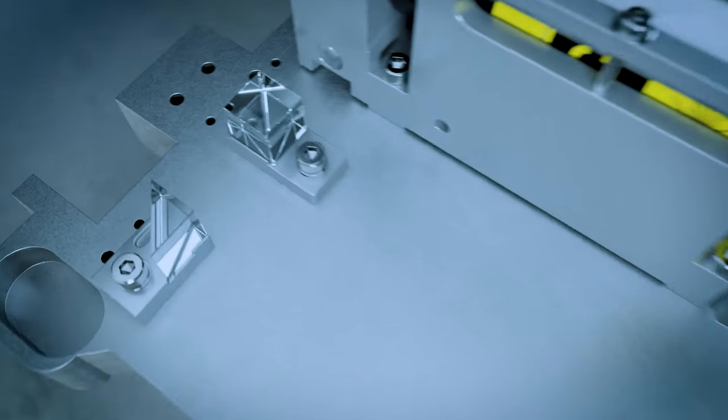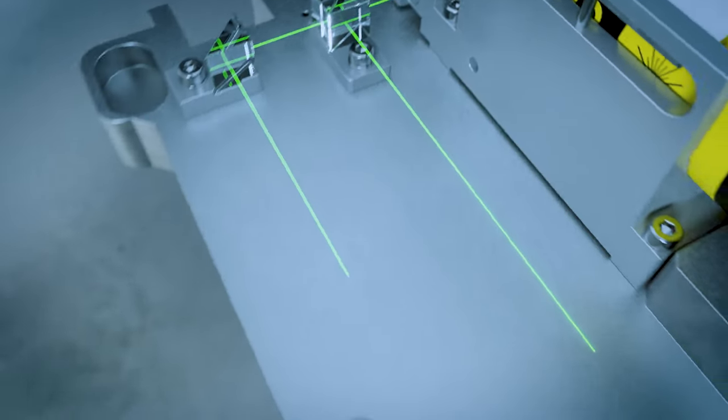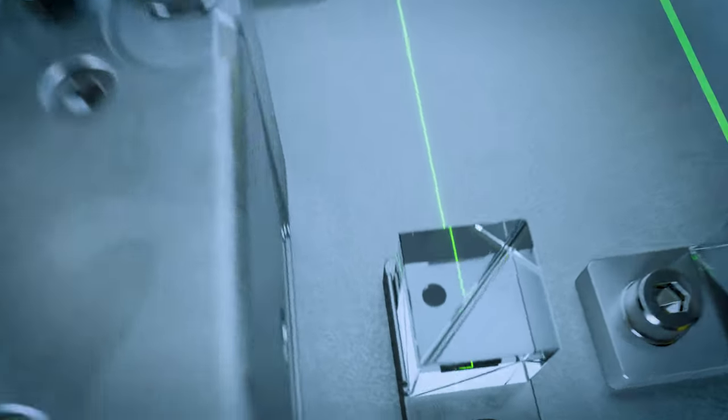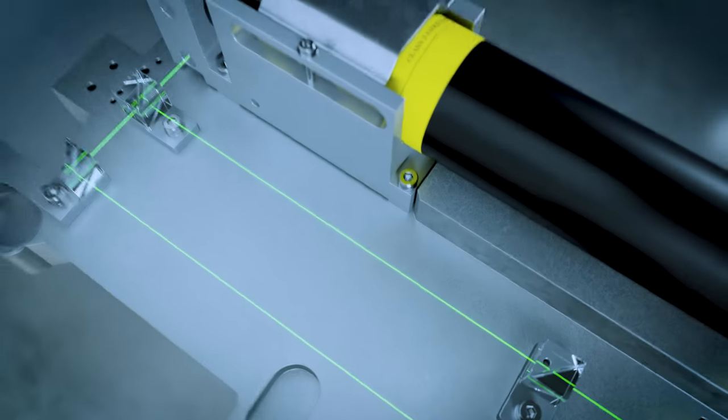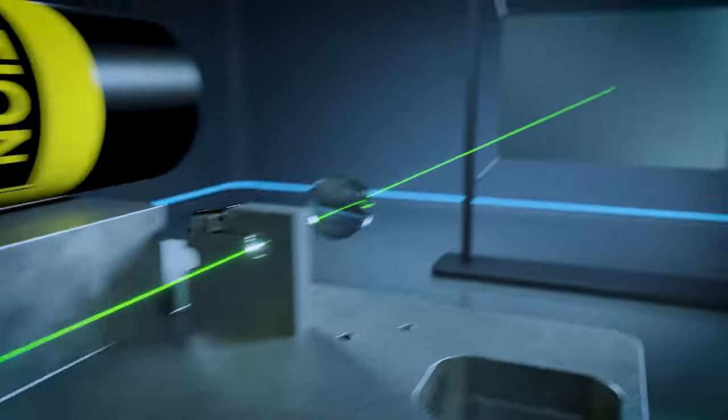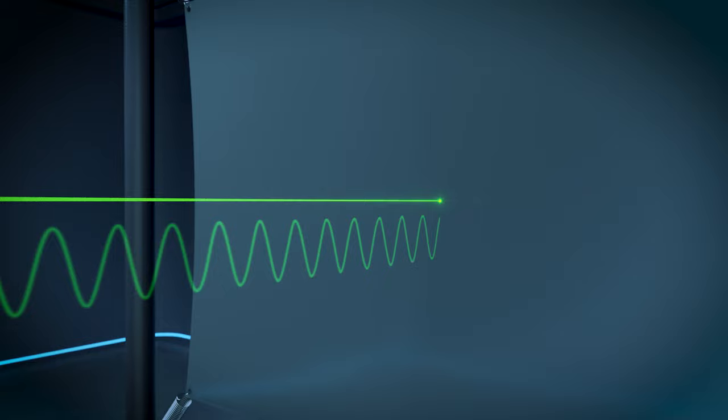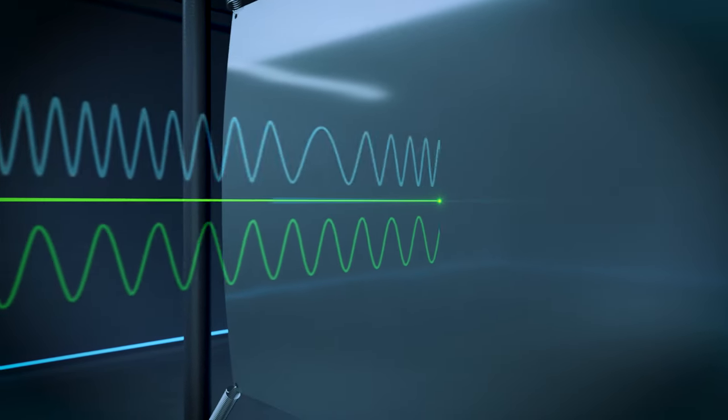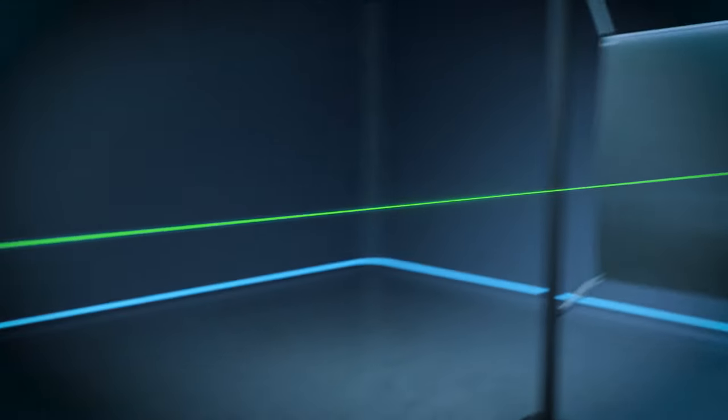To achieve this, the interferometer splits the light into two parts. The reference beam is pointed directly to the photodetector, while the measurement beam is incident on the test object, where light is scattered by the moving surface. Depending on velocity and displacement, the backscattered light is changed in frequency and phase.